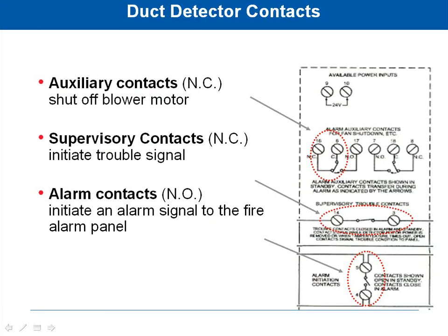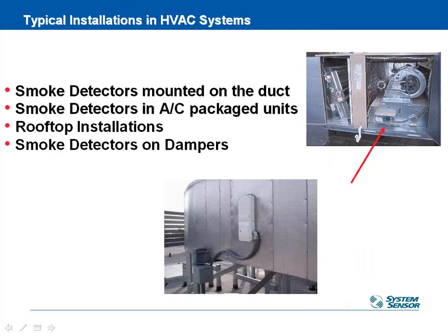Sometimes you'll have additional contacts on some smoke detectors to initiate remote alarm stations like strobes and horns, or to integrate to the fire life safety panel, or to interlock between different smoke detectors. You might have 3 or 4 of them on the same system. When one of them alarms, you may want all of them to alarm and shut off their associated air handlers. You can do that. So where to put these things?